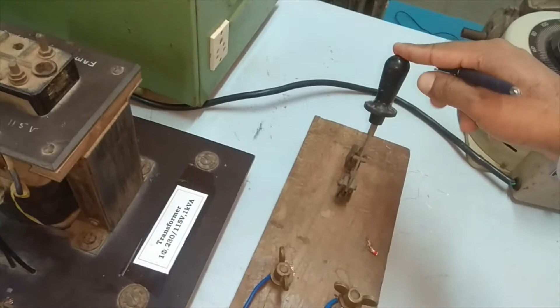If the voltmeter reads 0, it is properly connected. If it reads any other value, it means the secondaries of the transformers are wrongly connected. At that time, what would happen? If this switch is closed, a large circulating current will flow and the transformer may get damaged. That's why before closing, this switch should be open and the voltmeter should read 0. This is an important precaution for switching on the supply.